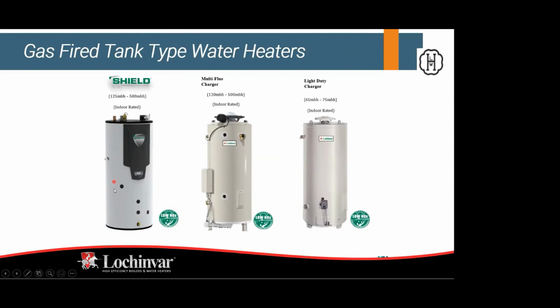You'll see manufacturers, I don't want to say play games, but get creative with how they market water heaters. This is a good example, and I'm not trying to push Lochinvar. We're just the rep, and Lochinvar just gets creative. Here's a good example of that in what they call the Shield. Looks exactly like a tank type water heater. If we went to look at recoveries, you'll notice that it's going to be quite a bit higher than a standard tank type water heater and more efficient. You wonder, so what's the magic under the jacket?